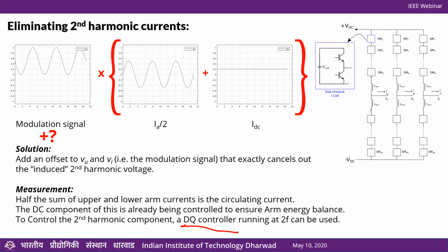The next question is, what is the reference frame for that 2F? Where should that controller's reference frame be aligned? The short answer is it doesn't matter, because what we want to do is create a new voltage to counter an unknown voltage that's already there. This is our 2F unknown, and this is our 2F star—my intervention—and it only has to counter the unknown. So essentially this should equal the negative of that, and we are good. It doesn't matter where my reference frame is, as long as it consistently rotates at double the fundamental frequency.